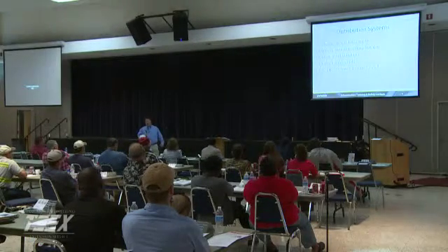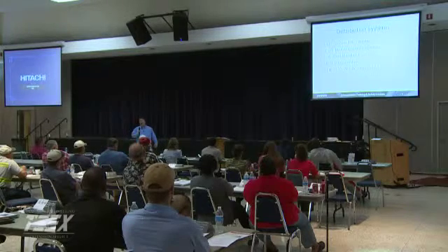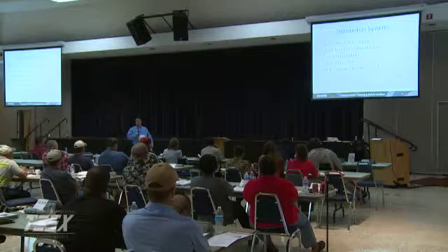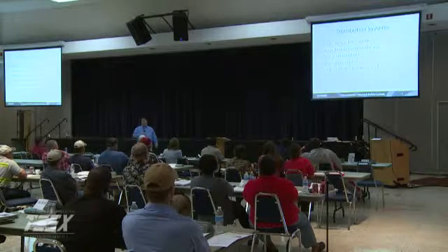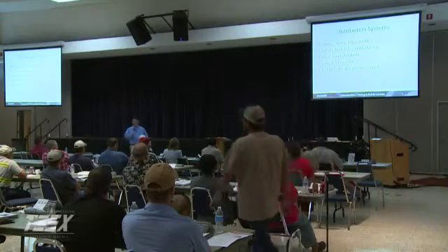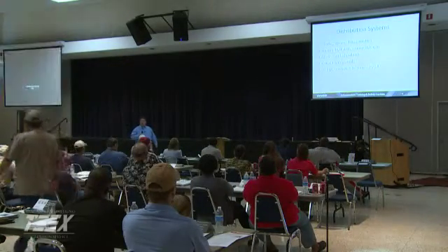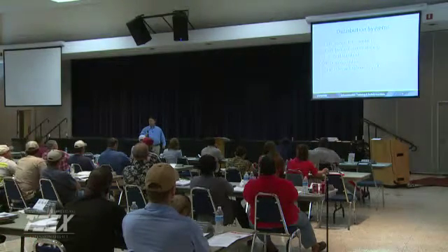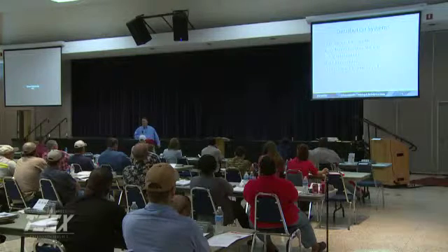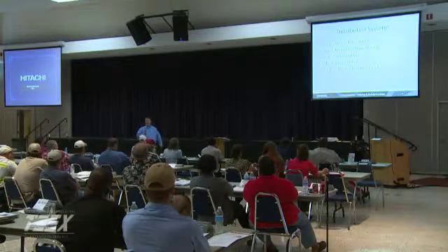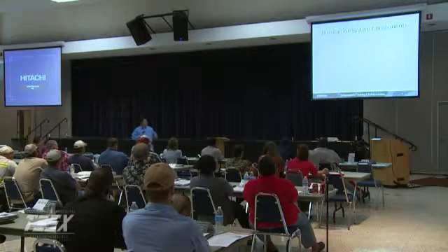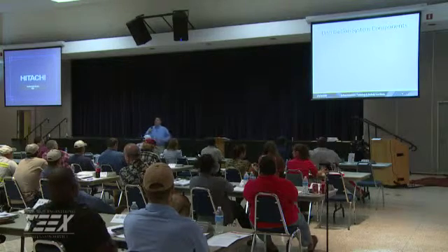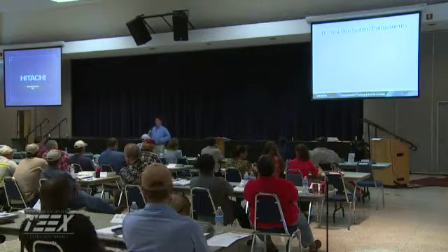What we go by as a rule of thumb, normally, well, actually it's a state regulation for us, but it's also what we try to go by, is 35 PSI under normal conditions. Then 15 or 20, depending on your state regulation, which 15 here, is for emergency situations like during extreme drought or during a hurricane, immediately after some sort of a disaster, something where you had to shut some equipment down, or you didn't shut it down but it went down on its own. Like I said, 35 is under normal conditions. 15 is for emergencies.